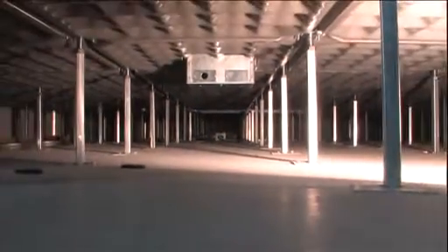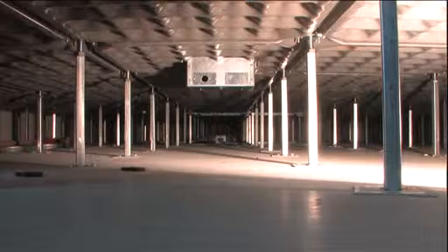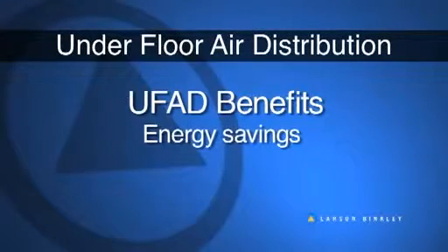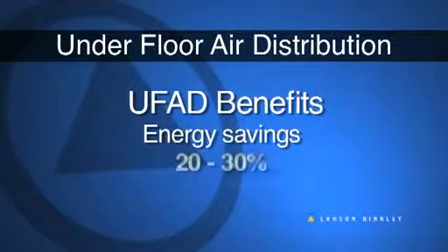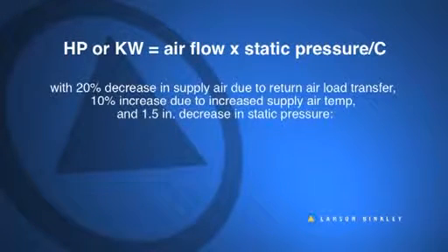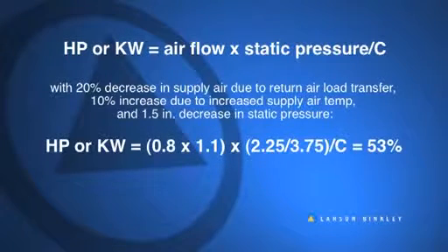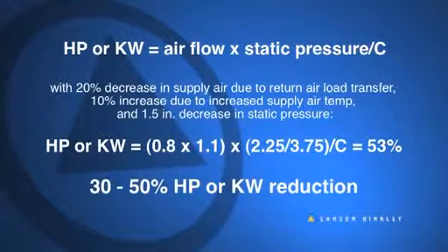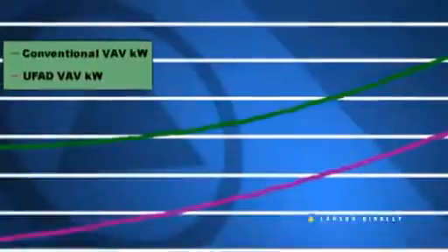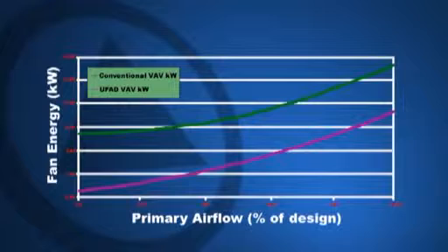That's a considerable savings. And as you can imagine, there are far fewer traffic jams and scheduling conflicts among the trades. Many developers find the ongoing energy savings the most compelling benefit of all. 20 to 30% energy savings have been experienced with underfloor versus overhead ducted systems. We know that fans use the greatest amount of energy in ventilation systems. With a floor static pressure of only 0.05 inches, the fan horsepower can be reduced by 30 to 50% over a ducted system, utilizing 1.5 to 2 inches of static pressure. This is why underfloor air has significant savings in energy usage versus conventional ducted overhead systems.